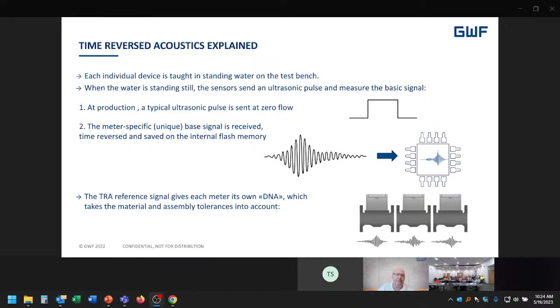Now, when we've got this fingerprint and you put this meter in the field, the reference signal is sent out and it goes across and back across the channel, from one side to the other. So it goes up with the flow and back against the flow. But rather than looking at a threshold as to when we start seeing the signal, we're actually looking at the signal itself and comparing it. So we're looking for the time shift between them.